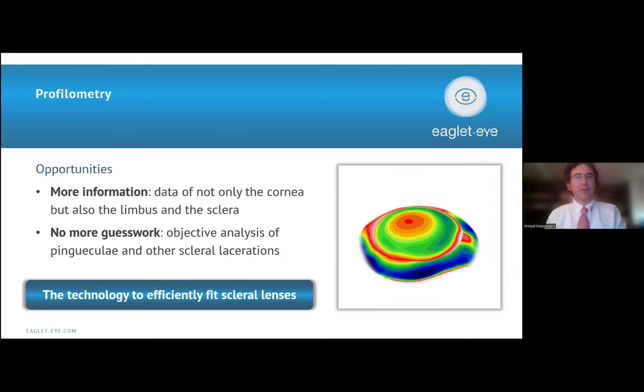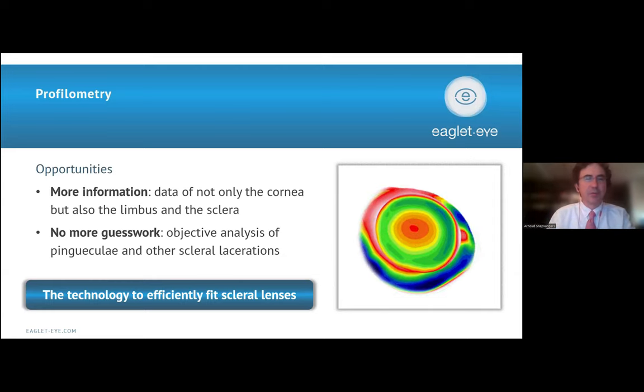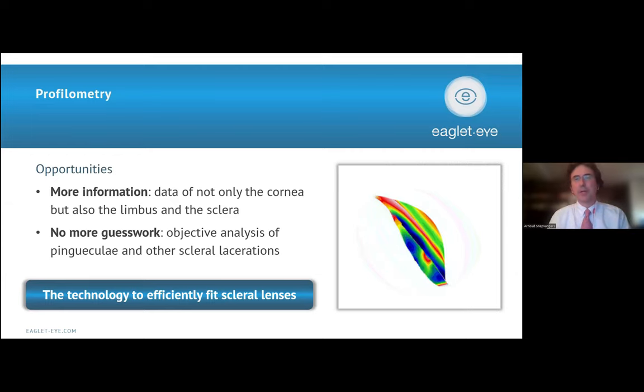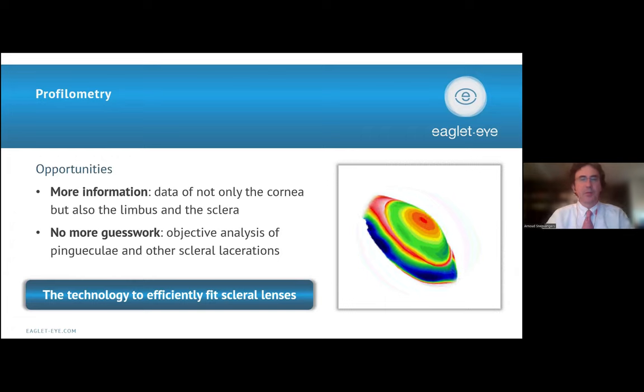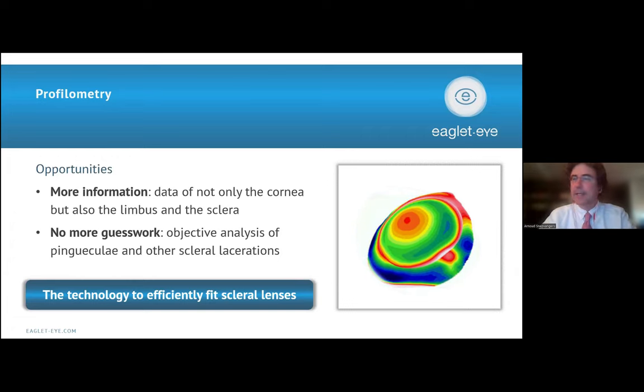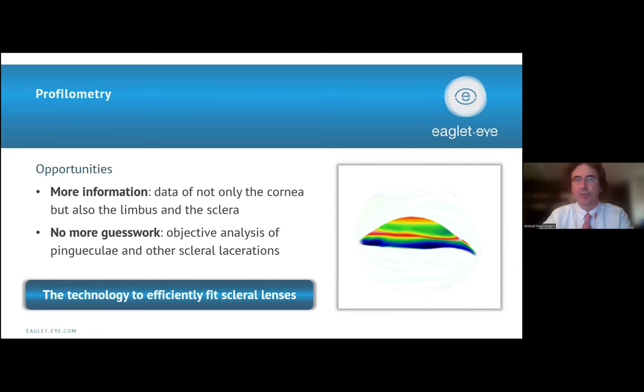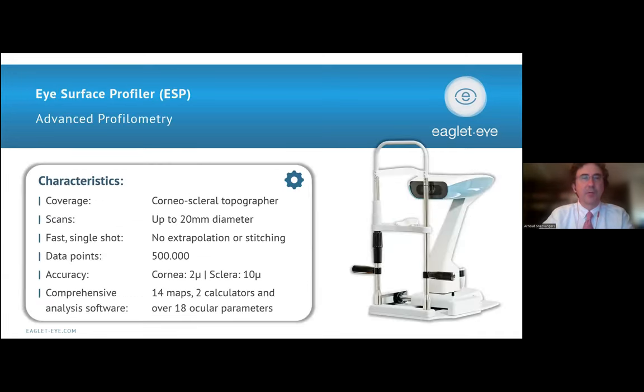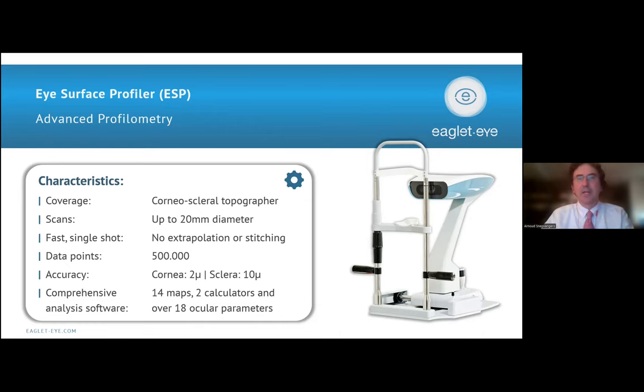The Eye Surface Profiler is based on profilometry. It measures the full cornea limbus to limbus every time, plus a large part of the sclera. With that 3D data of the ocular surface, you take away the guesswork of specialty contact lens fitting. It's a single-shot device — very fast — with 2-micron accuracy for the cornea and 10-micron for the sclera, and about half a million data points. It's also a full topographer with all the corneal maps and parameters of a normal topographer.